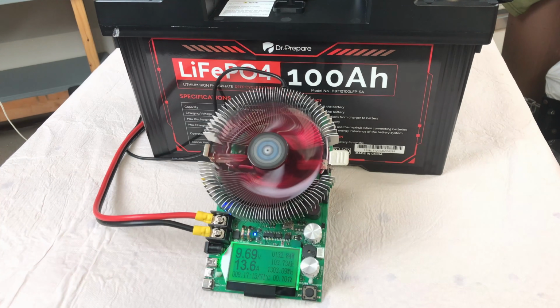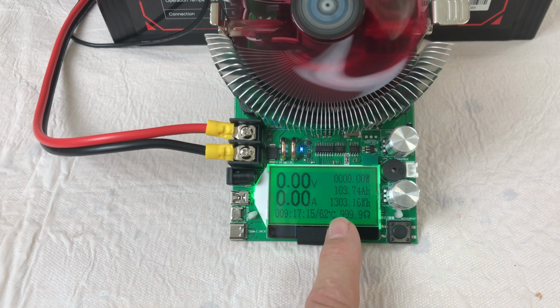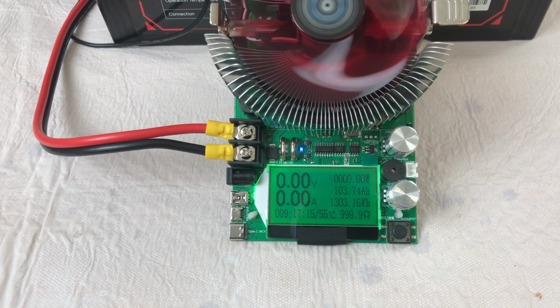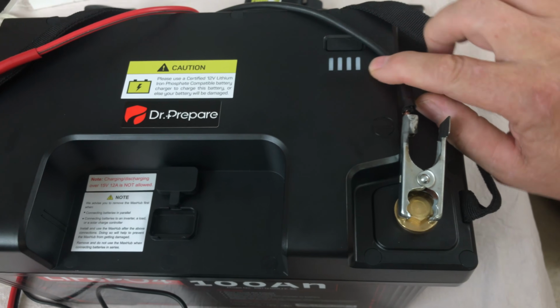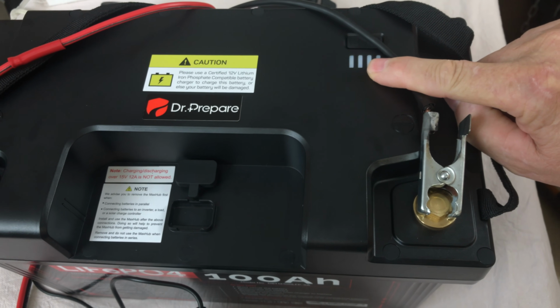I suppose the battery's going to shut down any minute. There it goes, so it just shut down. Let me zoom in and get you the total on that. So here's the final result: 103.74 amp hours, 1,303.16 watt hours, 9 hours and 17 minutes for the test. And if we look at the top of the battery here, one blue light blinking on the meter.